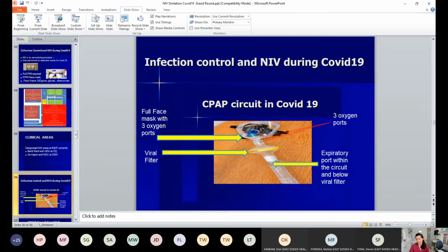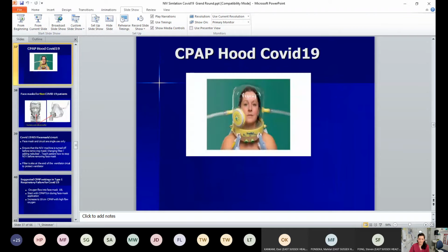You can see it's a full face mask. It's got 3 ports where the oxygen can go in. And it's got this yellow filter that filters out any viral particles the patient's breathing out. And the expiratory port, where the carbon dioxide comes out, is below the viral filter. So it keeps everyone as safe as possible. And we ask our patients and our nursing staff to turn off the ventilator before they take off the face mask to try and reduce contamination.